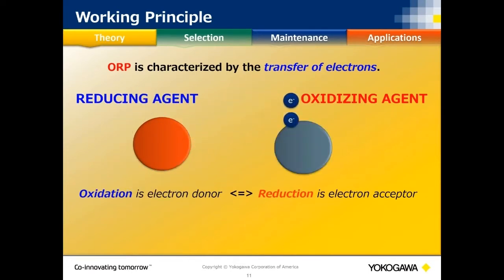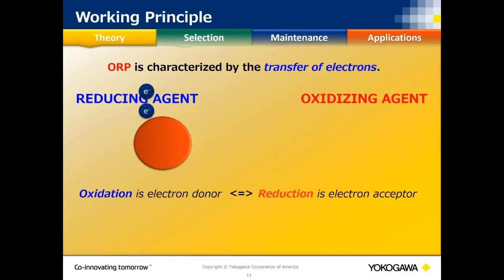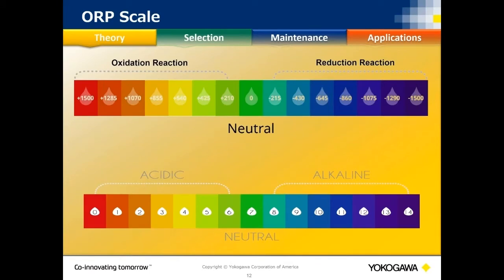The ORP scale normally goes from positive 1,500 to negative 1,500 millivolts, with 0 at the middle. A positive reading indicates an oxidation reaction — the element is giving up electrons. Anything below 0 is a reduction reaction. These reactions occur simultaneously, so the value the analyzer reads is the overall ability of the process to either oxidize or reduce.